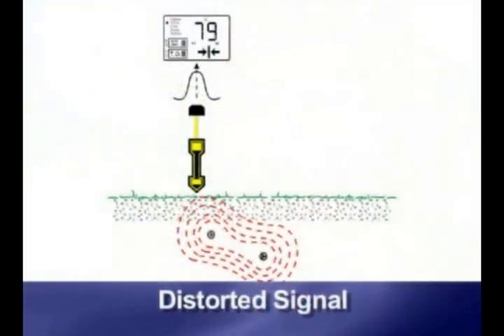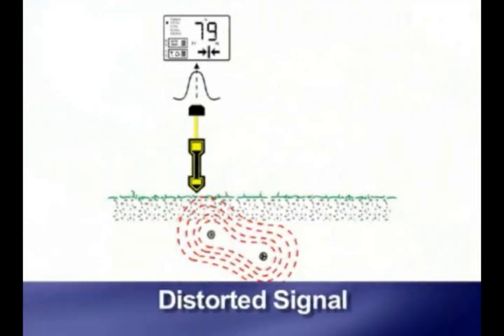Signal will abruptly stop at the open end. Here are some additional thoughts to keep in mind when using your Schonstedt locator: try to locate from the services outward to the utility source or feed, similar to telephone hookup practices. The same methods are used for cable, tracer wire, and fiber optics installed with shields, strength members, or tonable duct. Distorted signals where peak indications are erratic could be caused by various underground utilities merging and their geometry. Please refer to the manual for further details.